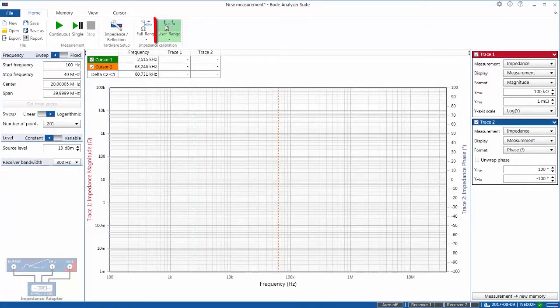So now you can see that now that you have calibrated this area has gone green to show that it is actually calibrated. Let's do a measurement to see if you read 100 ohms. Yes, we do see 100 ohms and the phase is zero so it's measuring correctly so that gives me confidence that the device has been calibrated properly.